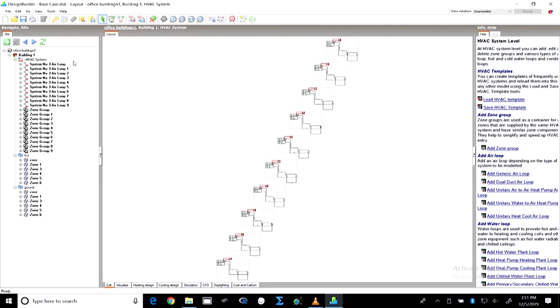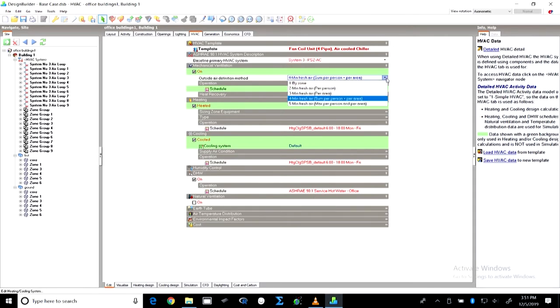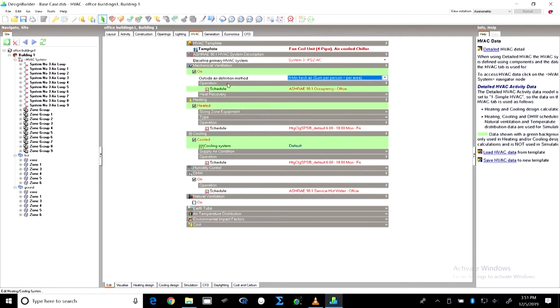The HVAC system is applied to all remaining zones automatically. Within the system detail we can change the coefficient of performance for each system. Along with this we can configure mechanical ventilation — heating and cooling are on for air conditioning. For outside air introduction, it could be per person, per area, or the sum of per person plus per area. This is dependent on the code — referring to NBC and ECBC, the minimum fresh air as sum per person and per area is applicable in our case.